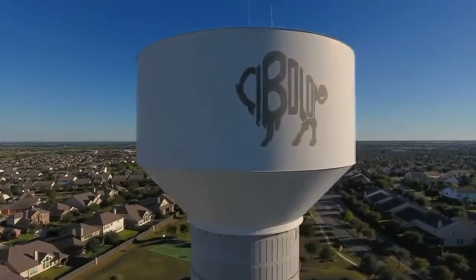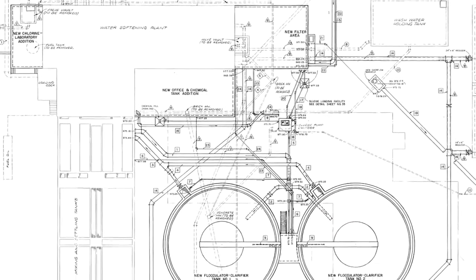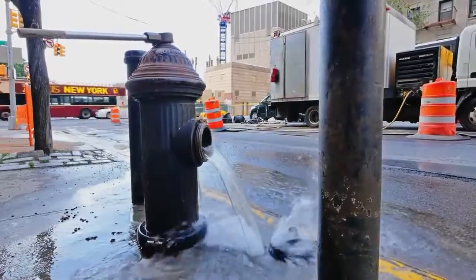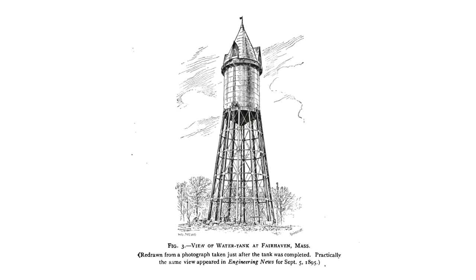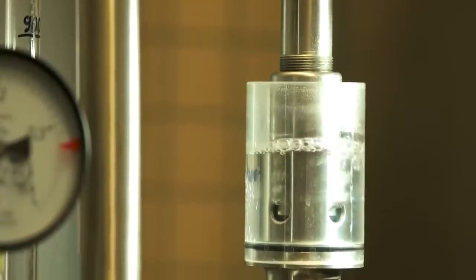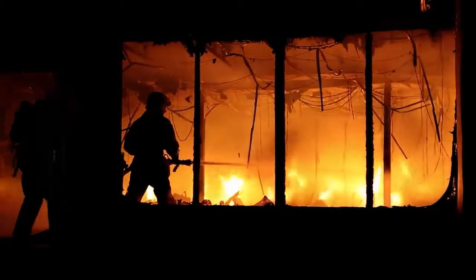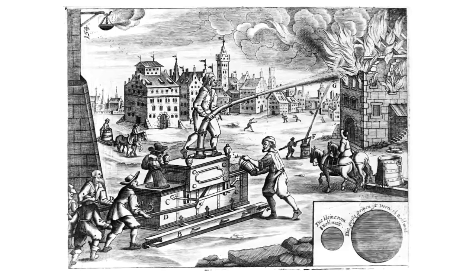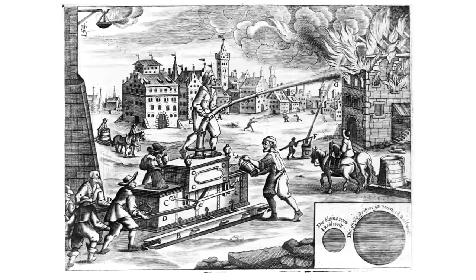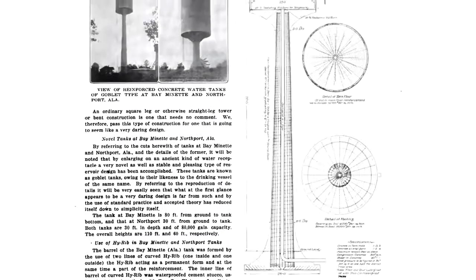It's pretty easy to see how storage makes your water system more efficient. It smooths out the peaks and valleys of water demand — not just on your pumps, but all your upstream infrastructure, including your water treatment plant and raw water supply. Without storage, all those facilities would need to be sized for peak demand, increasing their cost. With enough storage, pumps and other infrastructure can be sized for average demands, saving not only costs but also complexity, because you don't have to predict changes in demand and respond accordingly. Some of the biggest water demands in urban areas are from fires. Without a firefighting force and enough water to supply them, fires can burn out of control in dense urban areas. In fact, many of the deadliest disasters in history were fires in cities before modern water systems. Now most municipalities and building codes have minimum requirements for the amount of water that must be available to firefighters, and having water stored and ready, like in a water tower, goes a long way to being able to respond to an emergency.